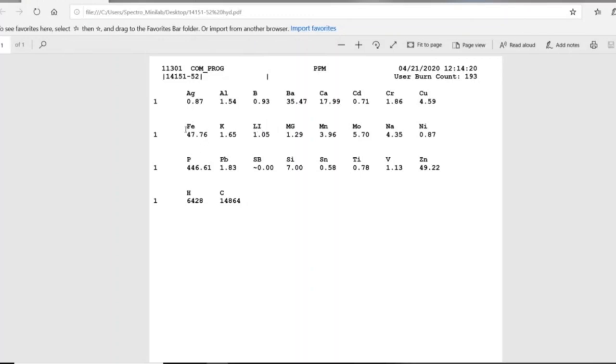Now, what's important to note with this is that all spectrometers have an inability to measure very large particles of iron if it's an optical emission system. The commercial labs can't really get data on anything more than about 5 microns.